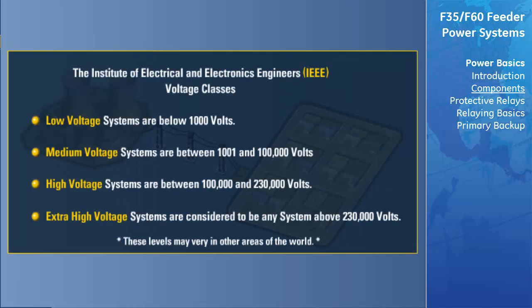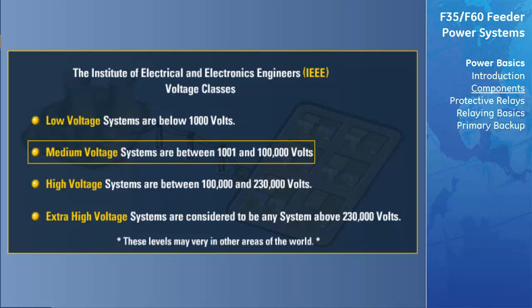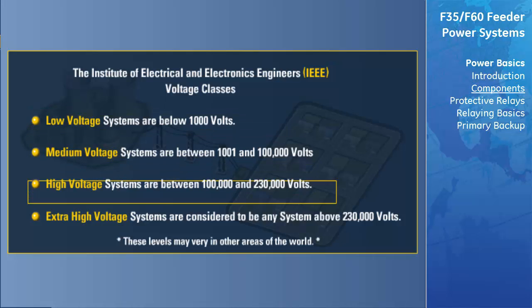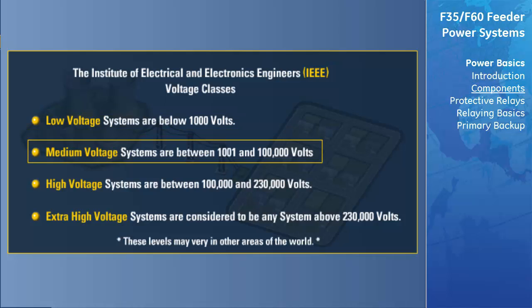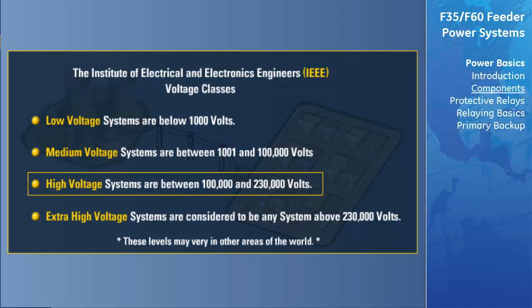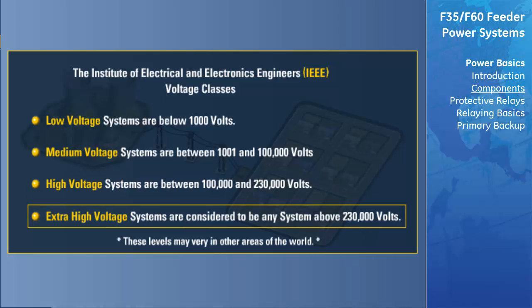The Institute of Electrical and Electronics Engineers, sometimes referred to as the IEEE, have divided voltage systems into low, medium, high voltage, and extra-high classes. Low voltage systems are below 1,000 volts; medium voltage systems are between 1,001 and 100,000 volts; high voltage systems are between 100,000 and 230,000 volts; and extra-high voltage systems are any system above 230,000 volts.